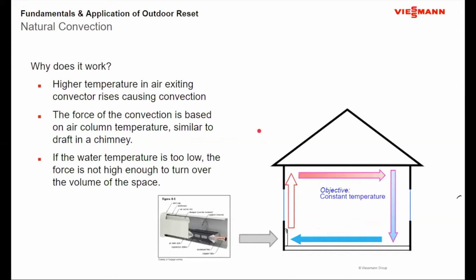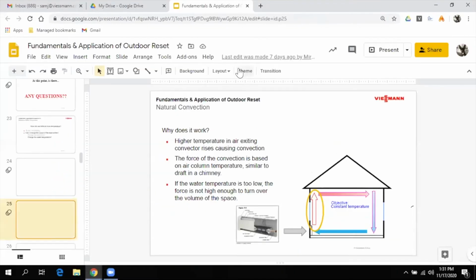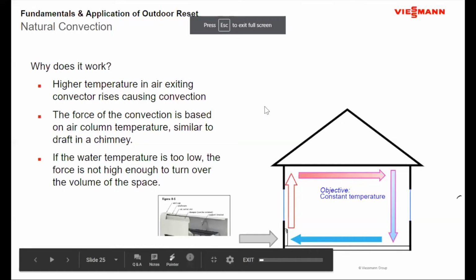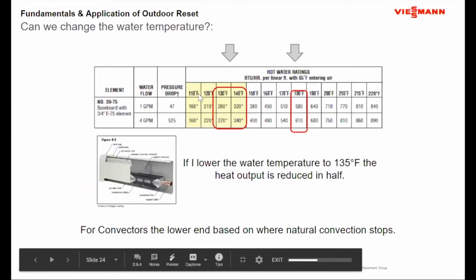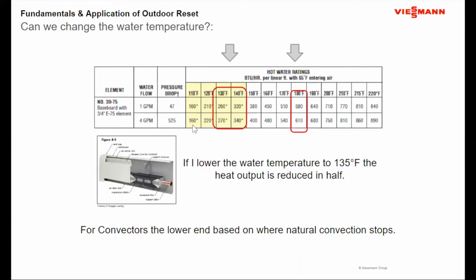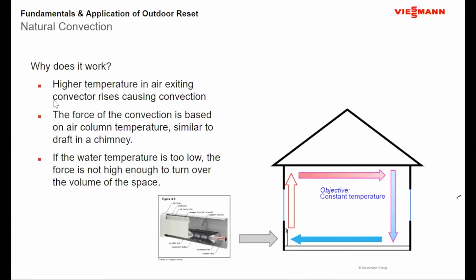So we start to look at doing outdoor reset with baseboard. You tend to see what you see here, where it doesn't go all the way down to 90 or 85 or 70 degrees Fahrenheit. It normally stops in the neighborhood of probably 105 to 110, as you see here. Okay. But from an aspect of performance, with outdoor reset, if I change the water temperature of the baseboard, I get a good corresponding change in the output of the heat emitter.